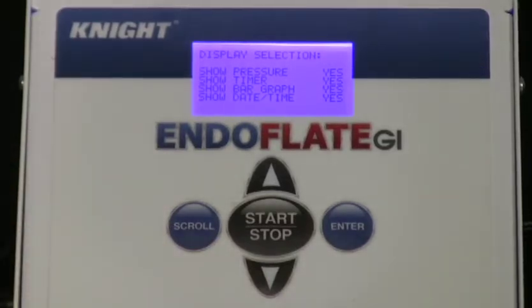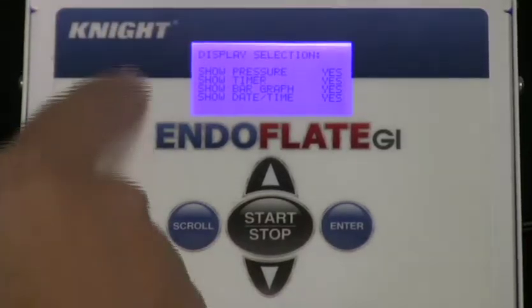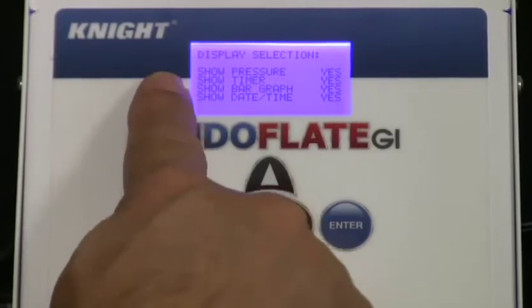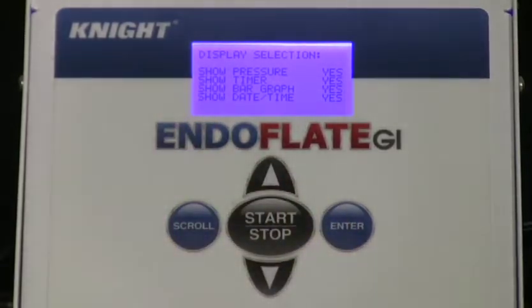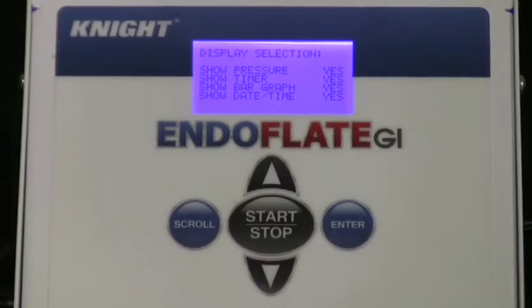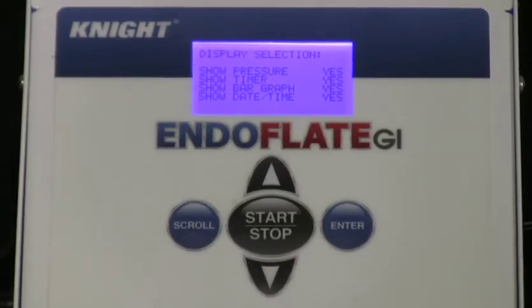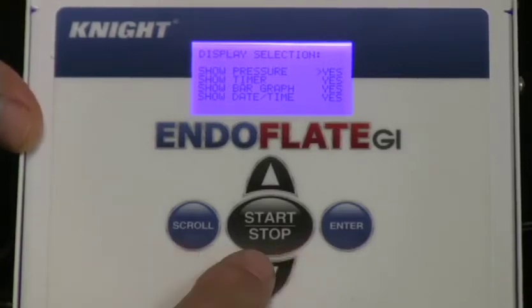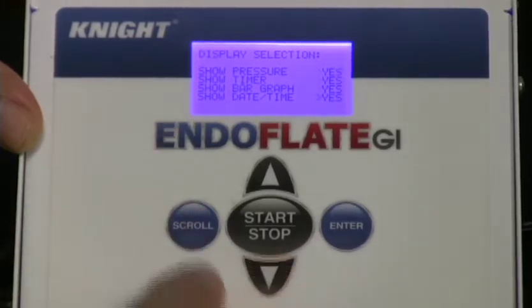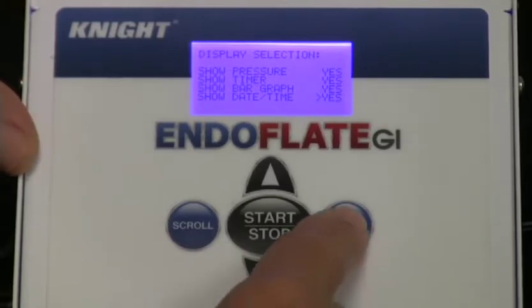On this next display selection, you can choose whether or not you want your user to see the pressure, to show the timer counting up, indicating how much time they've been doing the test. In a lot of cases, practitioners will dictate their procedure to have a time element. So as you see on this device, they want you to hold pressure for 2 minutes. You'll find that in a lot of places they want you to test for at least 30 seconds, maybe for a minute. It just depends, but at least by having that visual display, you can see how long the test went on. Okay, to make those changes, you first have to hit the arrow button to get the cursor in the top position, so you can hit scroll to leave it as a yes or no, and just go right on down the list and make your choices accordingly. Hit enter when you're done.